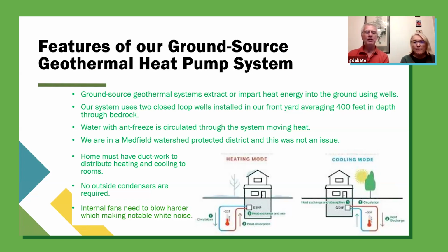So again, we're not experts, but here are some basics about our geothermal system. It is ground source, meaning you need wells—we have 2 that were dug, spec'd out at 400 feet deep. They go through bedrock, which is actually where the heat is sunk or pulled from, so it's important they get through it. They put antifreeze in the system. It's closed loop, and it moves around, basically moving heat from the ground to your house, or moving heat from your house into the ground—those are the two modes, heating or cooling.